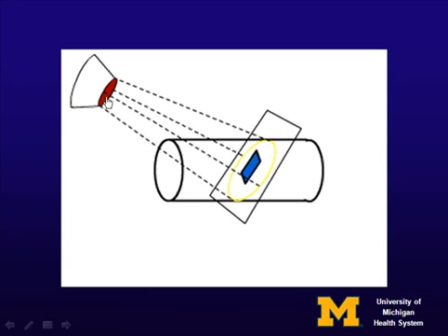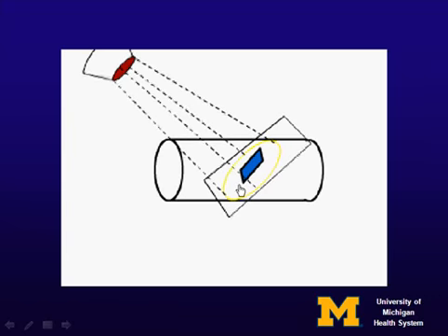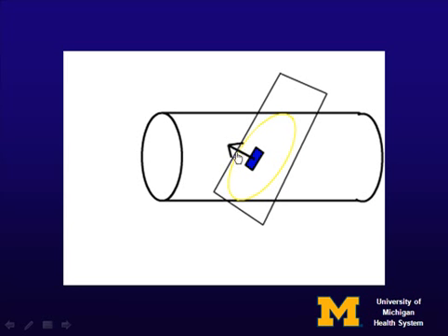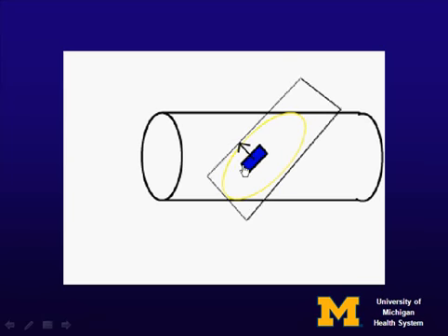To show that it's angle independent, we're now going to rotate the scan head, and you can watch the cross-sectional area get larger as we rotate the scan head. To make this more clear, if you use the normal component, that would be the component of the blood that's going perpendicular to this plane, which would be now right at the transducer. You notice as you rotate the plane, this component gets shorter. But this area gets larger in exactly the same proportion. And since it's the product of that component times the area, it's angle independent. So volume flow is angle independent, which is a huge plus.